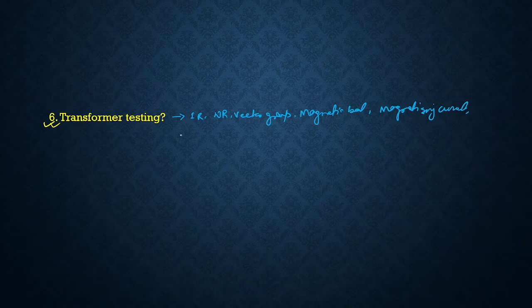Apart from these tests, we have some functional tests of the transformer, like Buchholz, PRV, WTI, OTI, MOG, and we check the alarm and tripping levels of these. And we also have some testing of the oil, while testing. Oil plays a very important role in the transformer. So these are the tests you have to go through if you are going to attend any interview.